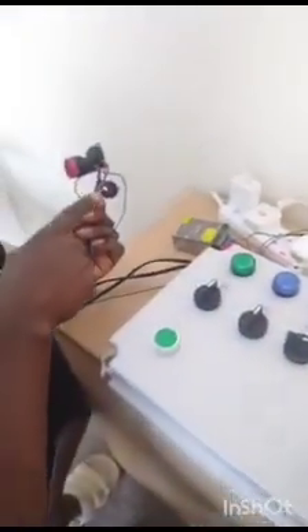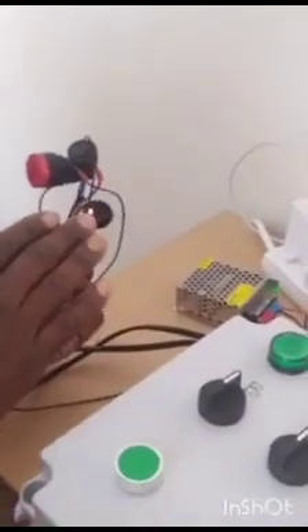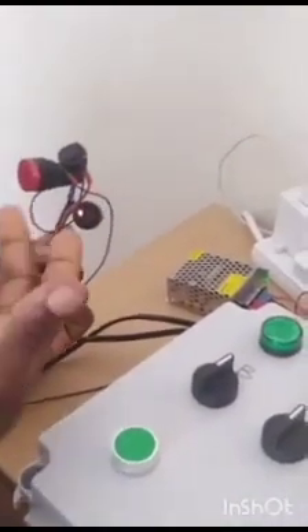So now let's start from manual. For the mode section, I go to the mode and check. You see this light represents the mode section, which is the coil, the valve controlling the mode section. It shows that it's working, there's power getting to the place. I check it's working, then I turn it off, then on again. It's all working well, then off again.